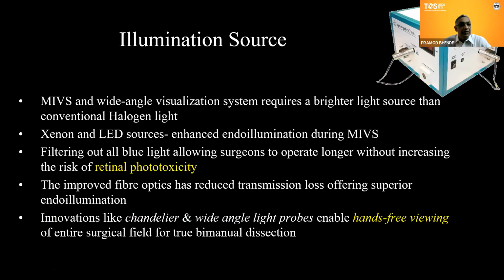Coming to illumination, obviously with MIVS and wide angle visualization system, we require much brighter illumination source than what we conventionally used to have as a halogen light. So xenon and LED is filling this gap. Also, most important is this filters out the blue light, which allows the surgeon to operate much longer without having a risk of retinal phototoxicity.